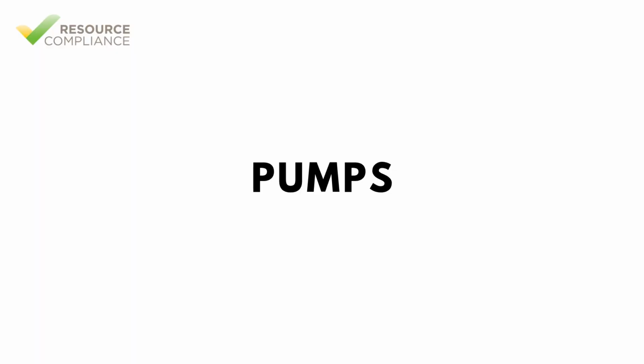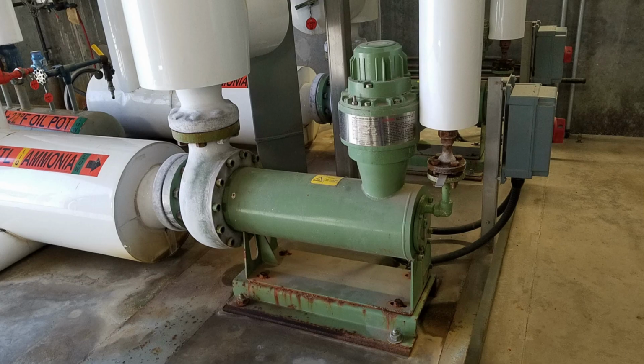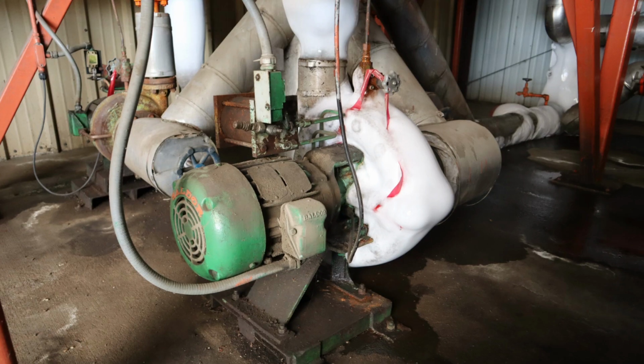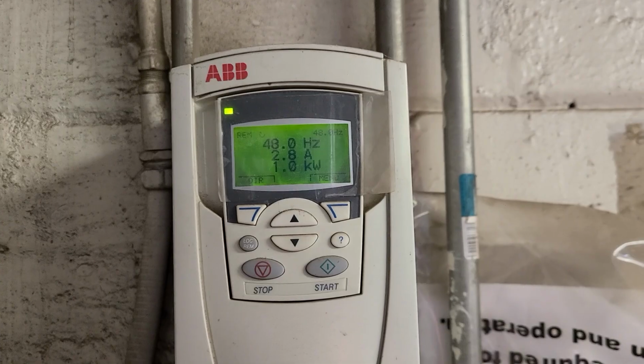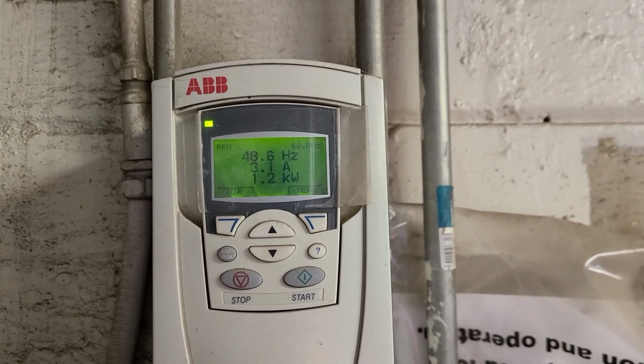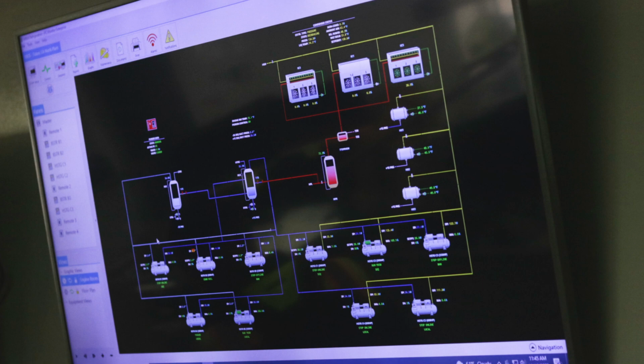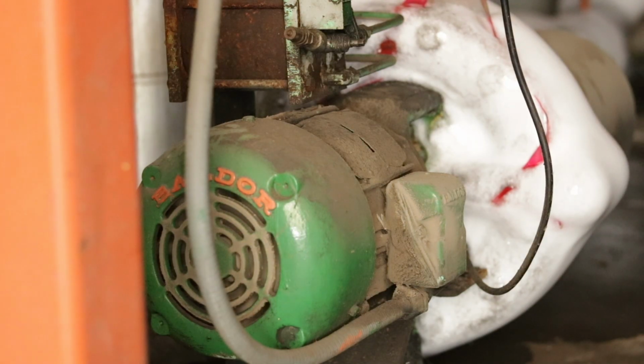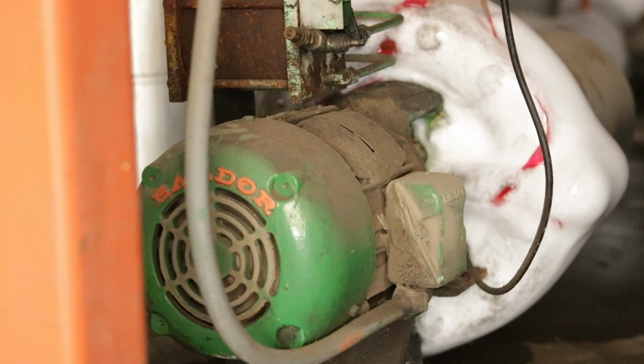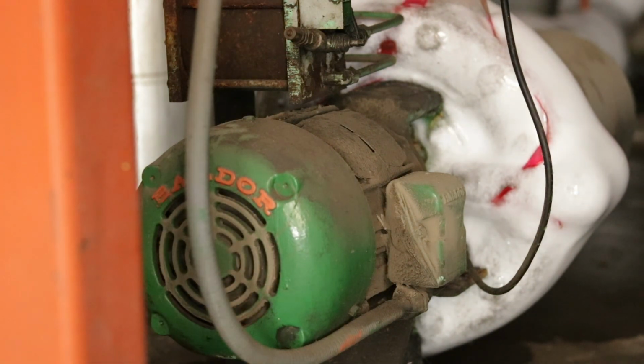The steps to follow when starting an ammonia pump will be specific to the pump manufacturer, but once in normal operation, the pump will start and stop automatically based on pressure differential, or may be controlled by a variable frequency drive, or VFD. For systems with PLC control, individual pumps are typically controlled at the HMI or from a dedicated pump control panel. Open drive pumps, such as the Cornell CB series pumps, which are widely used in ammonia refrigeration systems, have additional steps such as ensuring the oil reservoir is full and functional.